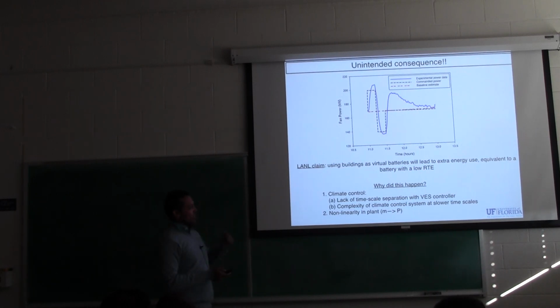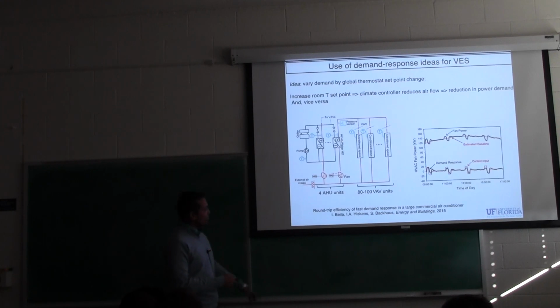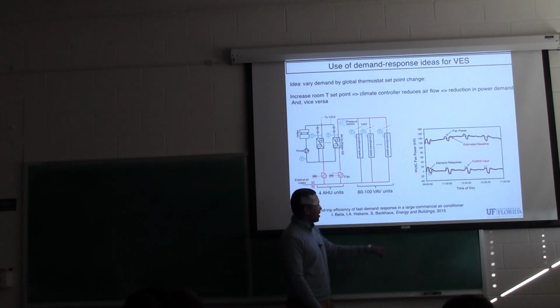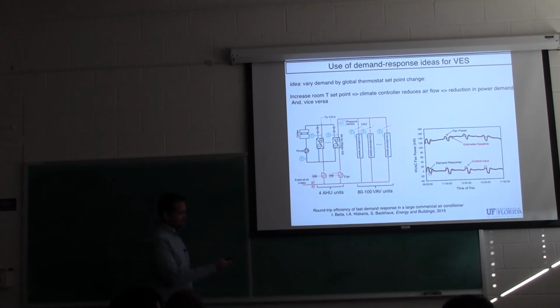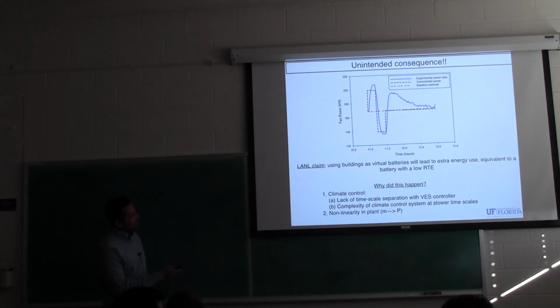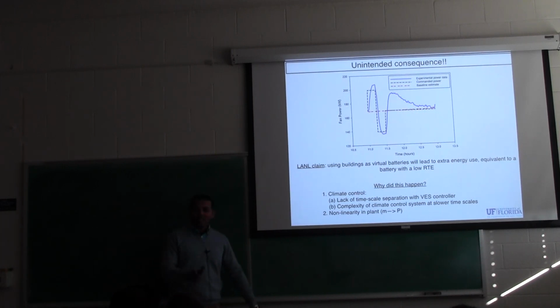So they say, well, look, this is bad because if you try to do this fast - this was their paper, round trip efficiency of fast demand response, a large commercial air conditioning system - then it's going to lead to this extra energy use, and therefore this is bad. You cannot do this.